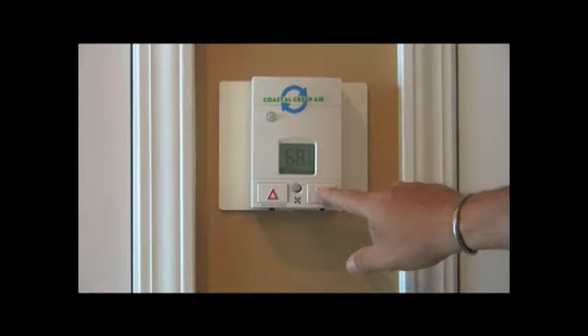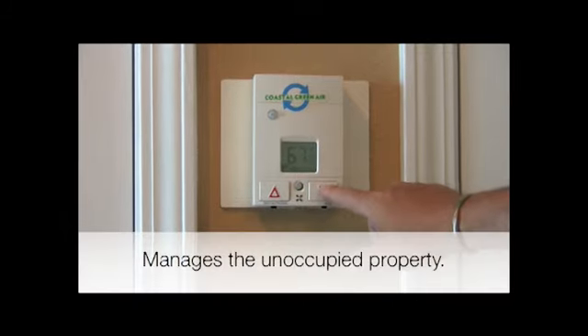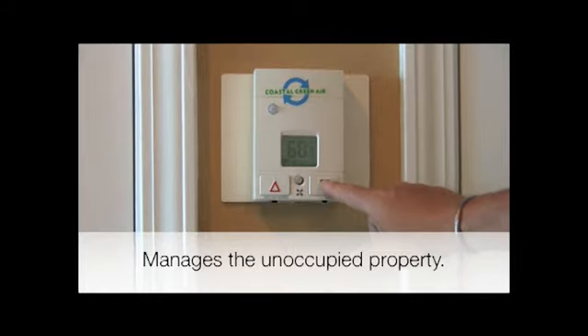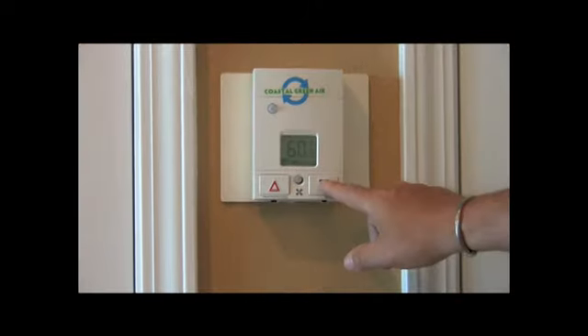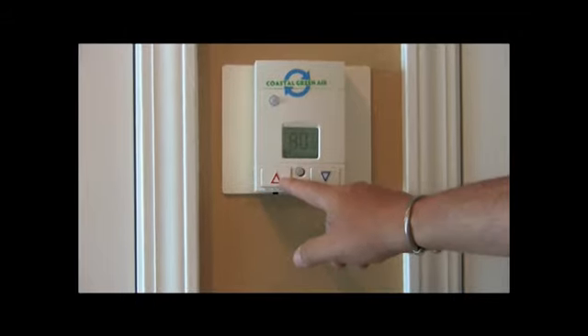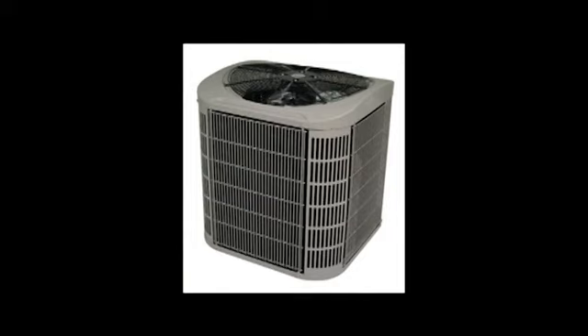The third thing our thermostat does is manage the unoccupied property after an additional 3 hours after reaching the unoccupied mode, for a total of 15 hours. Once the property is unoccupied for this total of 15 hours, the thermostat will make sure the HVAC works in the most economical way by monitoring the temperature of the property, managing the temperatures of 60 degrees low and 80 degrees high. If the temperature in the property goes below the low set point of 60 degrees or higher than the high set point of 80 degrees, the HVAC will respond accordingly and heat or cool the property to the set point as we mentioned in the unoccupied mode.